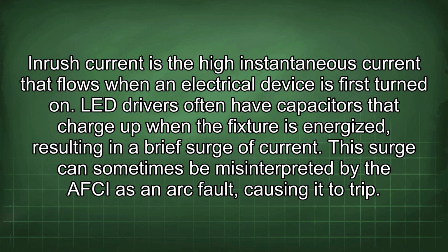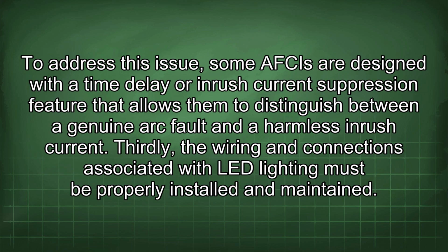LED drivers often have capacitors that charge up when the fixture is energized, resulting in a brief surge of current. This surge can sometimes be misinterpreted by the AFCI as an arc fault, causing it to trip. To address this issue, some AFCIs are designed with a time delay or inrush current suppression feature that allows them to distinguish between a genuine arc fault and a harmless inrush current.